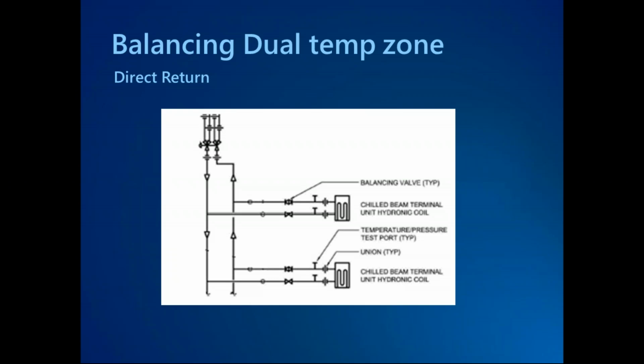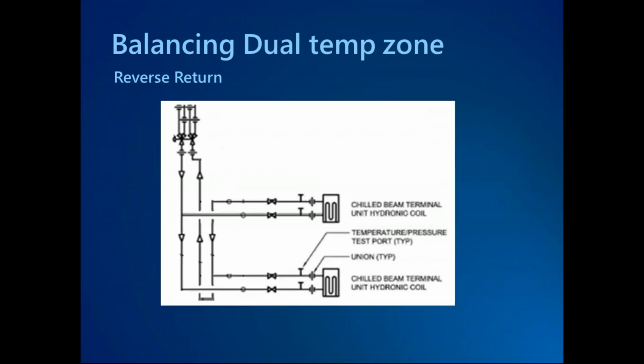If direct return piping is used downstream of this 6-way, then incorporating some sort of balance valve is recommended on every single chilled beam. You can go through and balance these to the higher of the 2 GPMs and just use proportional balancing to get the relative GPM for each chilled beam to be the correct ratio when it comes to comparing it to its neighbor. And then when you switch from cooling to heating or high flow to low flow, whatever it might be, the system downstream of the 6-way is still going to stay balanced.